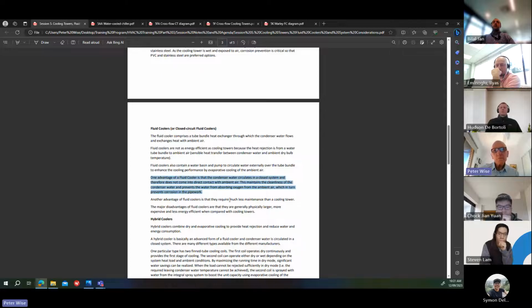A fluid cooler requires much less maintenance than a cooling tower, so that's another advantage. The major disadvantages with fluid coolers are they're generally physically larger than a cooling tower, more expensive and less energy efficient when compared with cooling towers.